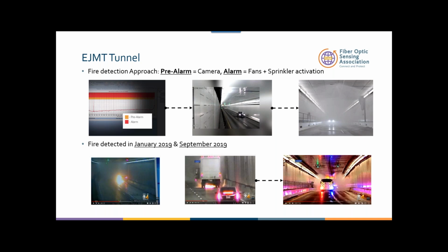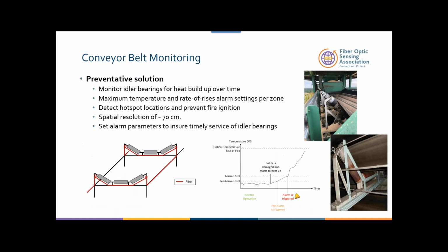From a trial point of view, these pictures on the top show that yes, you can get a pre-alarm, you activate the camera, and then you have a sprinkler system. At the bottom, we can see a real-time event and a real problem happening in the real world. And the EJMT, which is the number one tunnel in America, has firefighters being able to come in and intervene while the fire is being suppressed. Extremely important. The second application is conveyor belt monitoring.